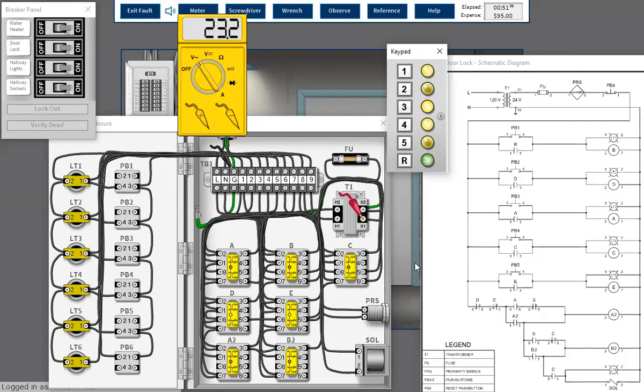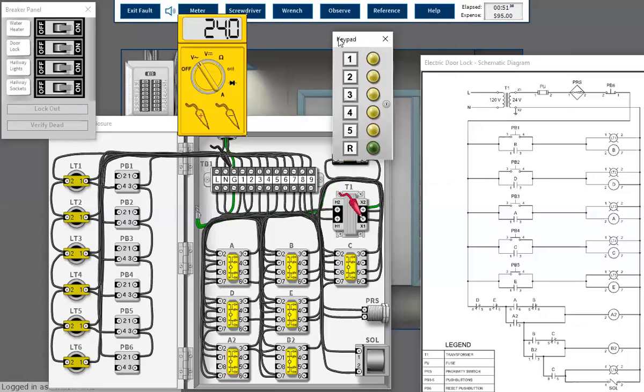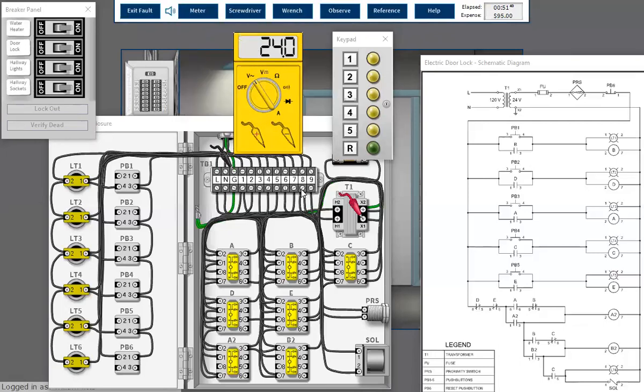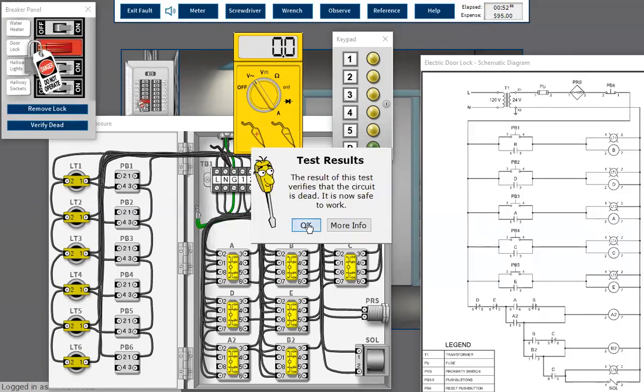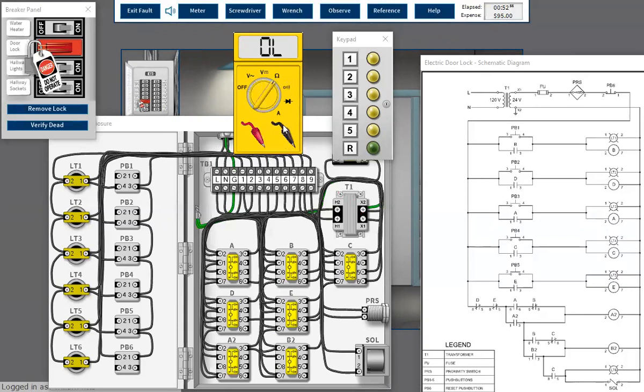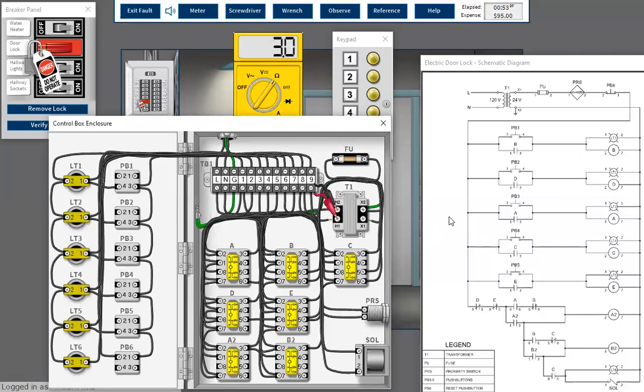I guess that's it. Man, I got my butt kicked on that one, guys. All right, so when I checked everything, being low, let's go back. Let's lock that out and look at it. So that's one of my faults, is I should be checking that transformer and see what the winding is, 0.5 on the secondary, which seems awfully low to me. But maybe it is.